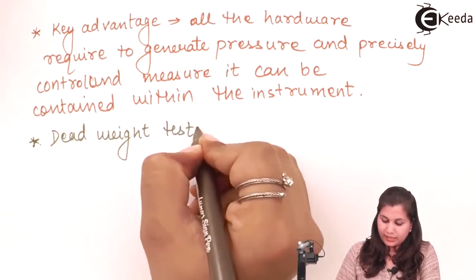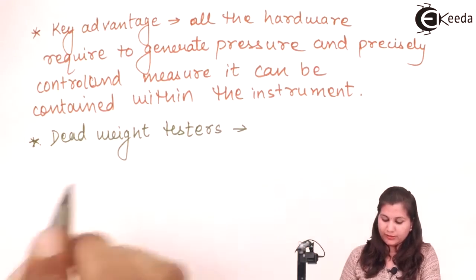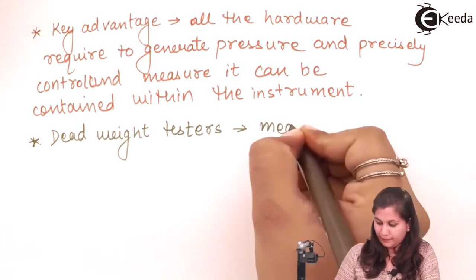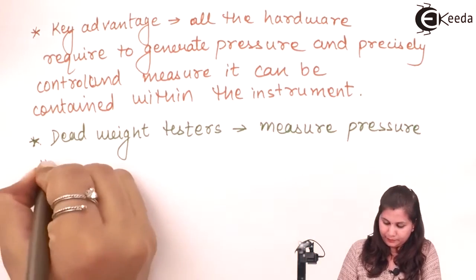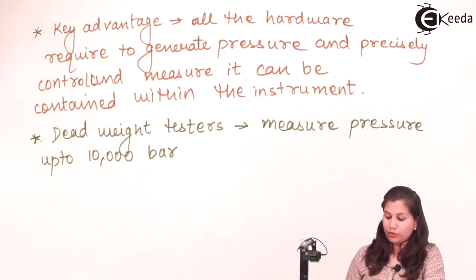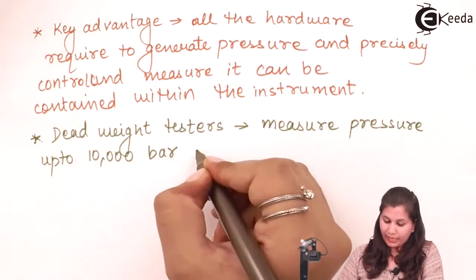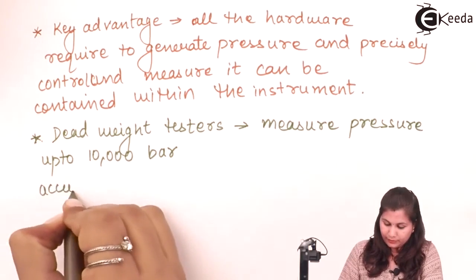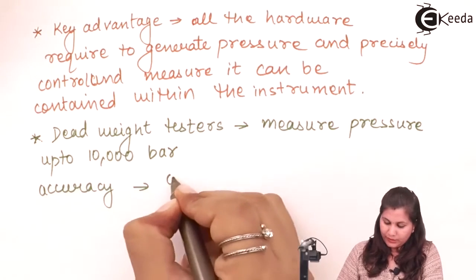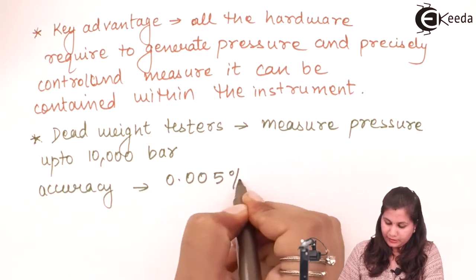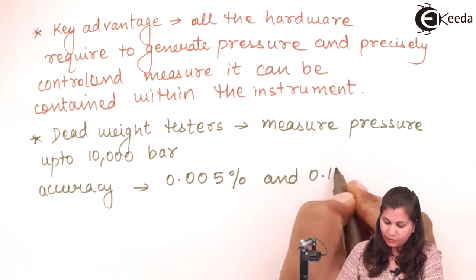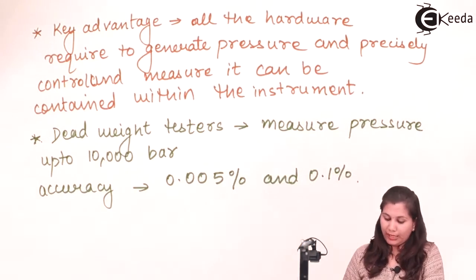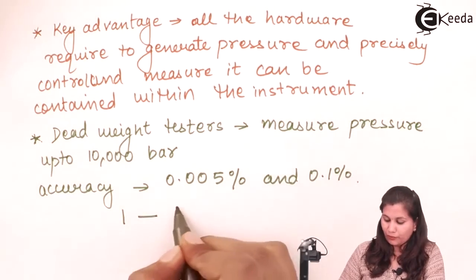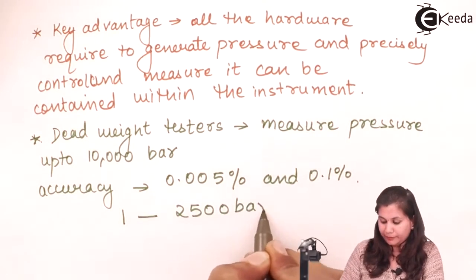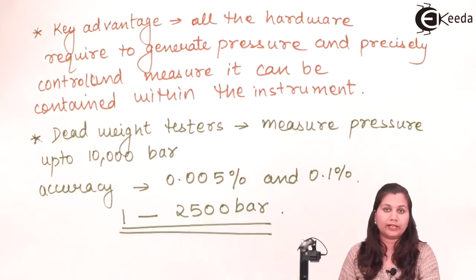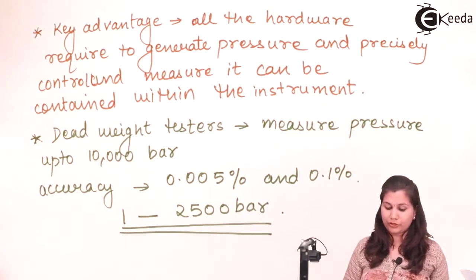Now the dead weight testers are used to measure pressures up to 10,000 bar, giving accuracies between 0.005% and 0.1%. Although in most of the applications, the pressure lies in the range from 1 to 2500 bar. So this is the pressure range in which the dead weight testers measure the pressure values.